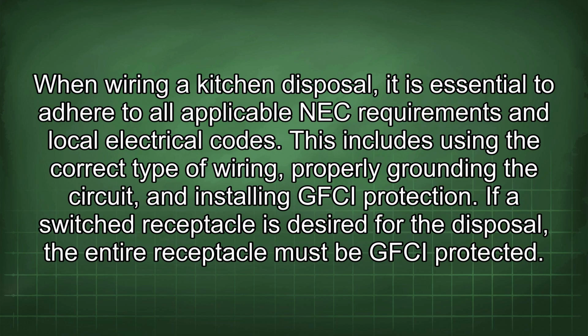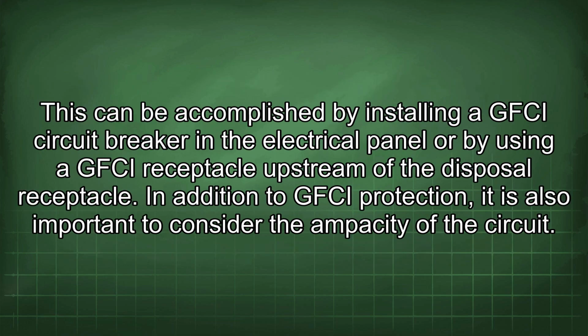When wiring a kitchen disposal, it is essential to adhere to all applicable NEC requirements and local electrical codes. This includes using the correct type of wiring, properly grounding the circuit, and installing GFCI protection. If a switched receptacle is desired for the disposal, the entire receptacle must be GFCI protected. This can be accomplished by installing a GFCI circuit breaker in the electrical panel or by using a GFCI receptacle upstream of the disposal receptacle.